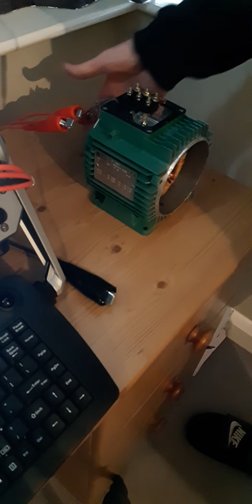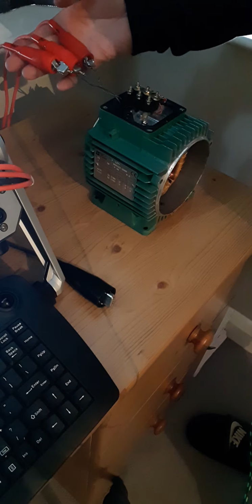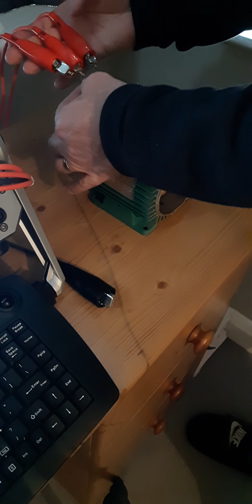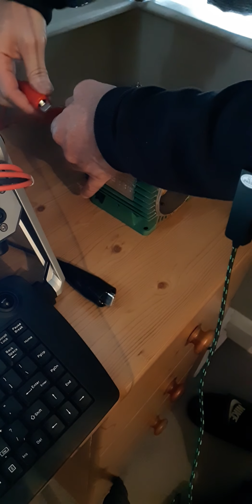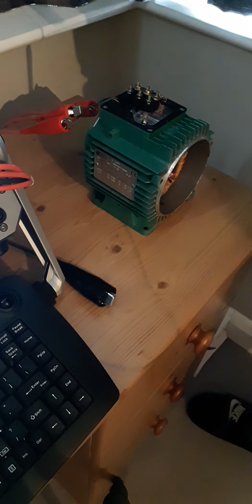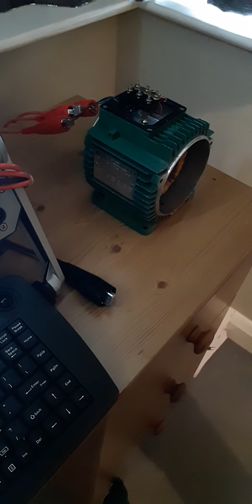I made that with my stator connected 1, 2, 3, so lead 1 to brown, 2 to blue, 3 to black. What I'm going to do now to simulate a fault is put 2 to brown, 3 to blue, and 1 to black. So instead of 1, 2, 3, it's 2, 3, 1. And that should simulate a fault, and we can see how the tester software deals with it.